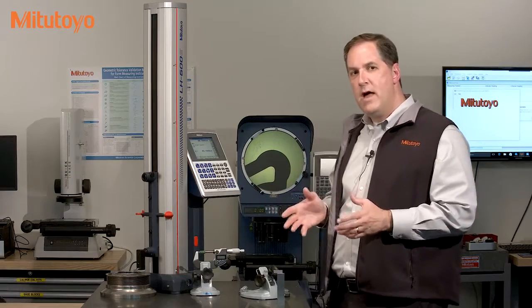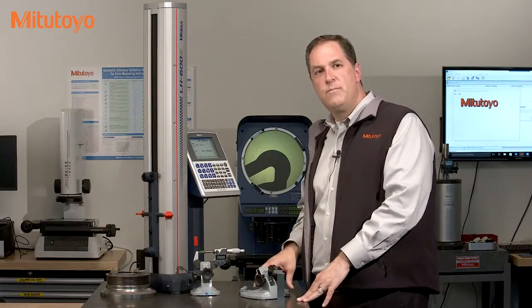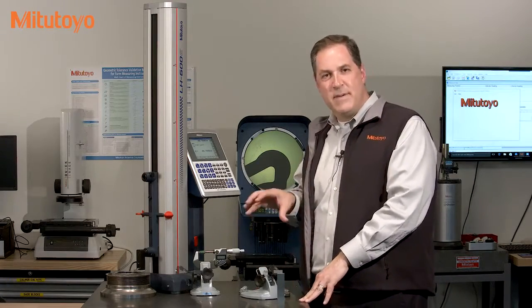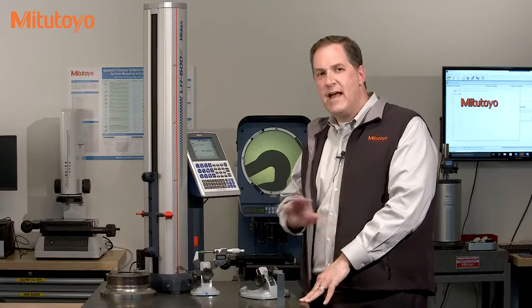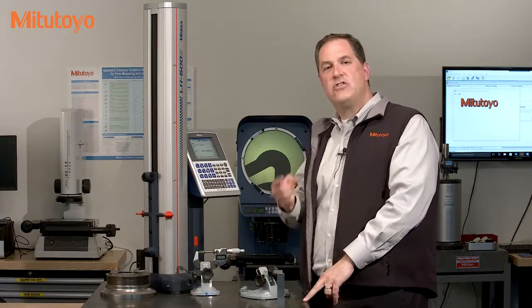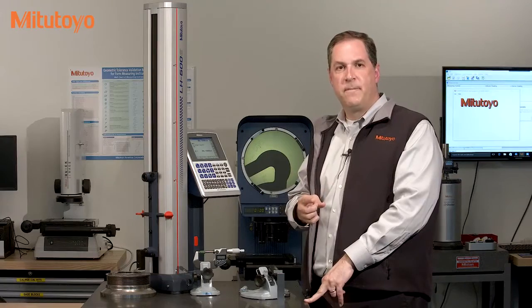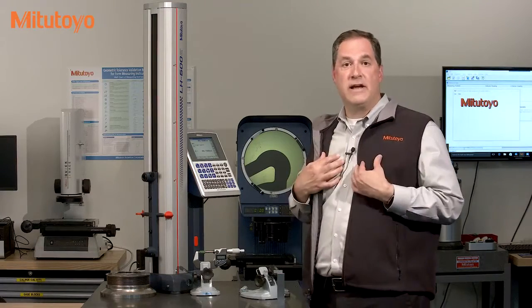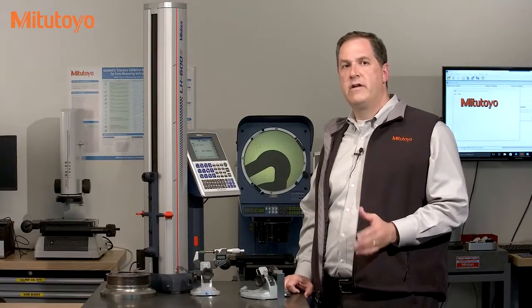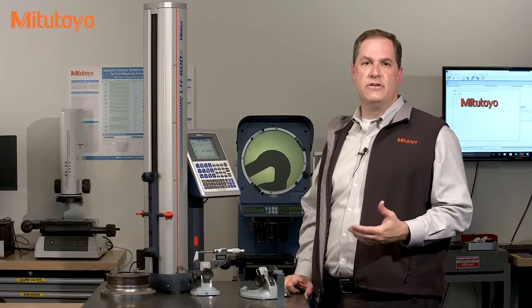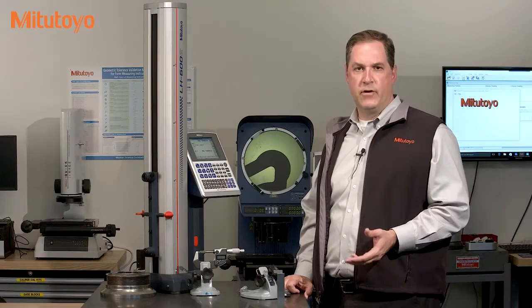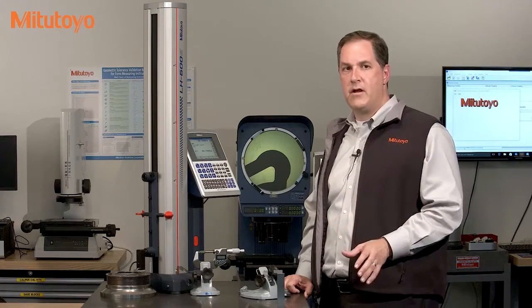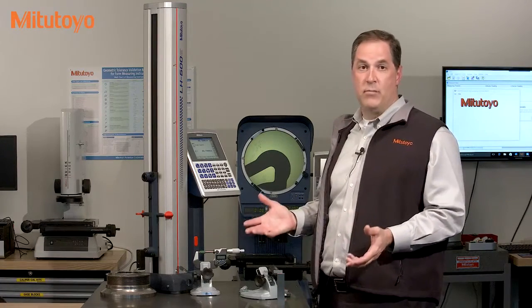In general, measuring equipment should perform within its specification over the lifetime of the equipment. That should be your expectation. That at least is definitely our expectation here at Mitutoyo America. Except in some very rare cases, you should never need to derate the accuracy of your measuring equipment, assuming you've taken proper care of it and assuming it was well built to start with.